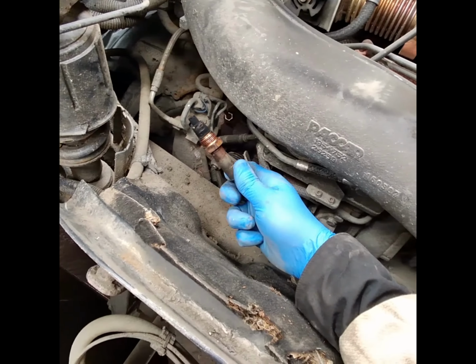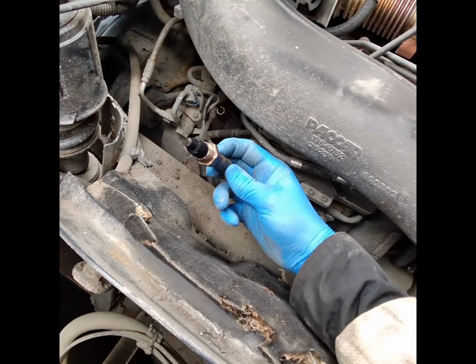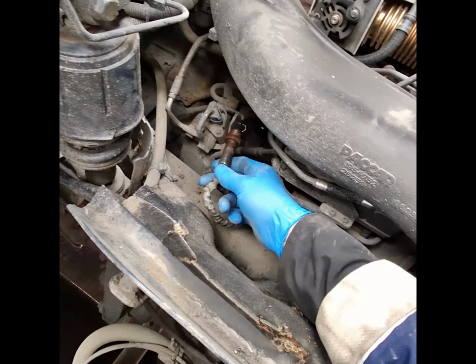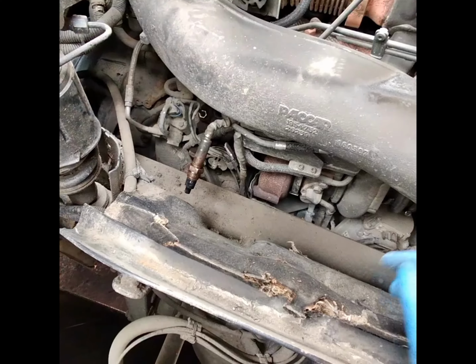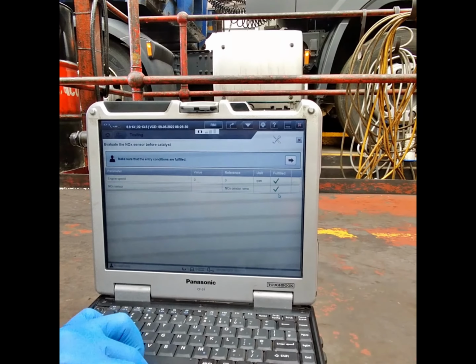To make sure that a failed conclusion of the test is not caused by sensor tip contamination, repeat the test 2 times, and if it still fails on the 3rd time, replace the sensor.